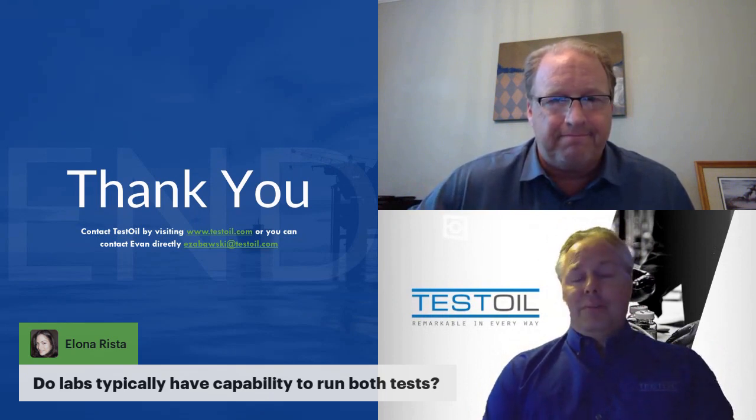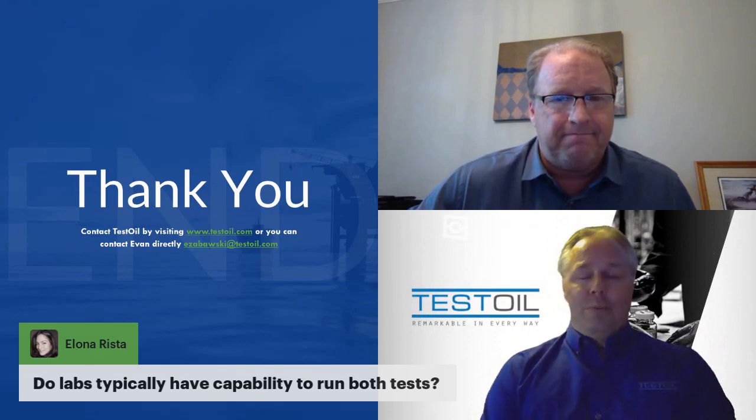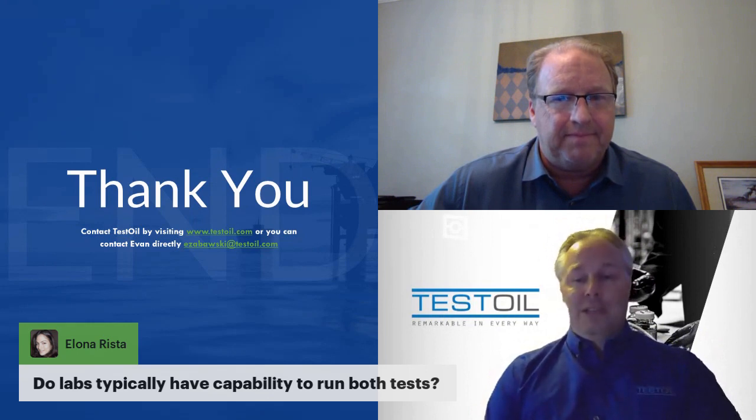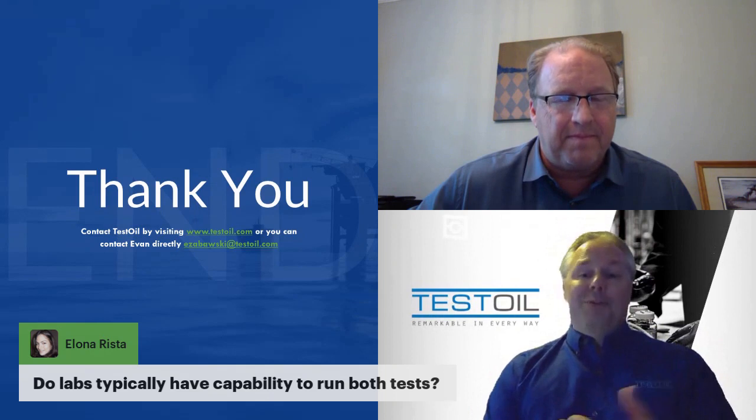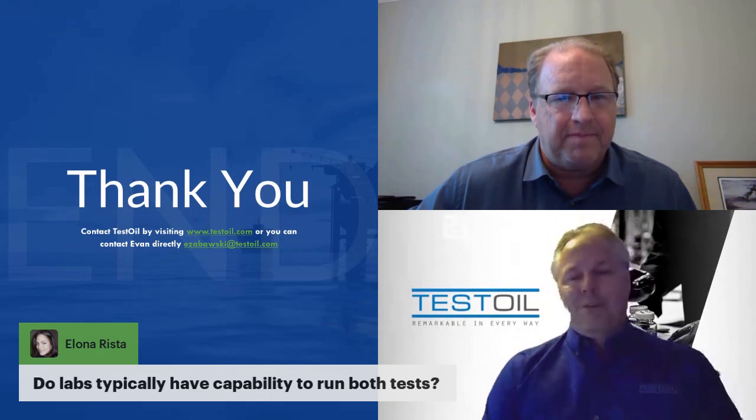Some of the dirtier type of samples like engine oils and gear oils, some labs won't run particle count on those oils, or particularly viscous oil samples, some labs don't run. So it's a good question to ask the lab that you're dealing with. Do you run this type of particle counting, whether you want to do pore block or optical, and is there ever a time you won't run it? We at TestOil, we run everything. We have ways around almost any hurdle, so we run everything.